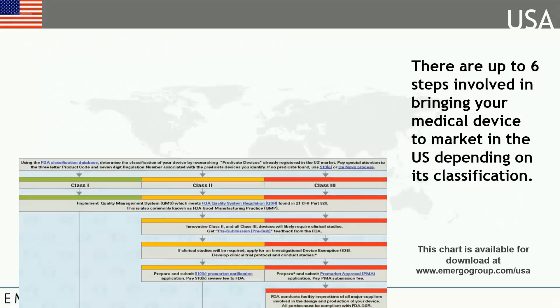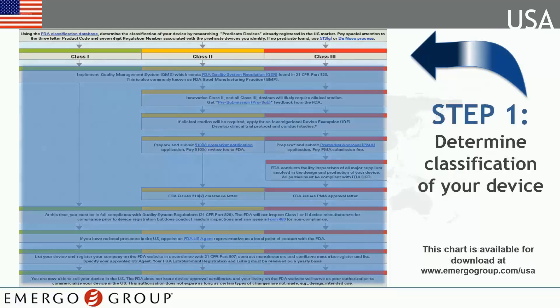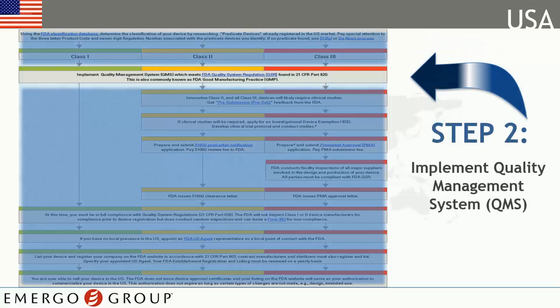The entire process of bringing your medical device to market in the U.S. can be summed up in six steps, all of which are covered in later modules within this course. Step one is device classification. The way the FDA classifies your product lays the groundwork and determines the number and complexity of the requirements for the rest of the process. The second step is the implementation of a quality management system. The FDA requires a QMS prior to selling your product in the U.S., so strict protocols must be followed regarding documentation, among other key aspects of the product lifecycle.